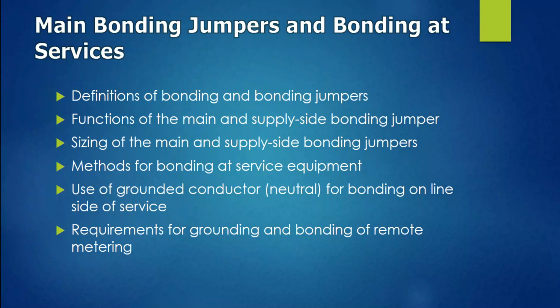So main bonding jumpers and bonding at the service, that's the scope of this training today. We're going to look at some definitions of bonding and bonding jumpers, the functions of a main and supply-side bonding jumper, what they do, and sizing those jumpers. We're going to look at the methods of bonding at service equipment, most notably on the supply side of that service equipment, including the use of the grounded conductor, or the neutral in some cases, for bonding on the line side of the service equipment, all the way up to the transformer, but mostly for us as electricians, up to the weatherhead.